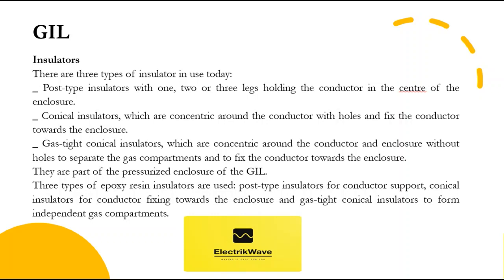For applications in GIL, the maximum temperature and the discharge tracking withstandability are the prime features, while mechanical strength and electric insulation are of minor importance. The mechanical strength for insulators in gas insulated switchgear is higher, where besides gas pressure, strong shock forces from circuit breakers and switches also need to be covered. There are three types of insulator in use today: post-type insulators with one, two, or three legs holding the conductor in the center; conical insulators which are concentric around the conductor with holes fixing the conductor towards the enclosure; and gas-tight conical insulators which are concentric around the conductor and enclosure without holes, to separate gas compartments and fix the conductor — these are part of the pressurized enclosure of the GIL.